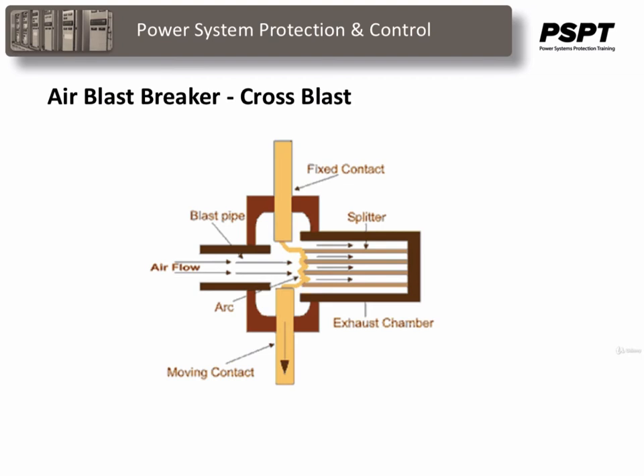When the moving contact is withdrawn from the fixed contact, an arc is established in between the contacts, and at the same time, high pressure air coming from the blast pipe will pass through the contact gap and will forcibly take the arc into the exhaust chamber, where the arc is split with the help of the splitters and ultimately quenched.